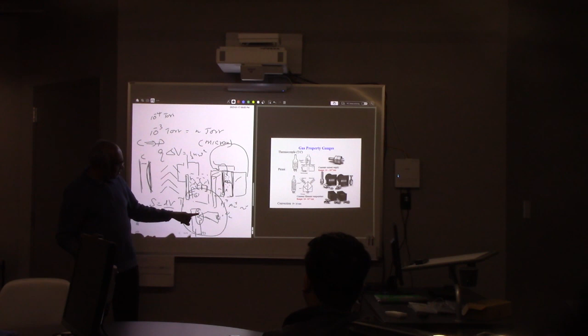Because this is connected to your system, this is where the pressure is going to be measured. If it has a lot of air molecules, when you heat the filament, that heat will be transferred to those gas molecules. So if you have a lot of gas molecules, a lot of heat gets transferred to them, which means the filament's temperature will be lower.